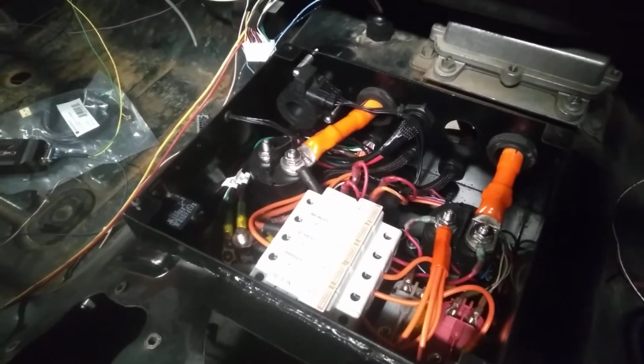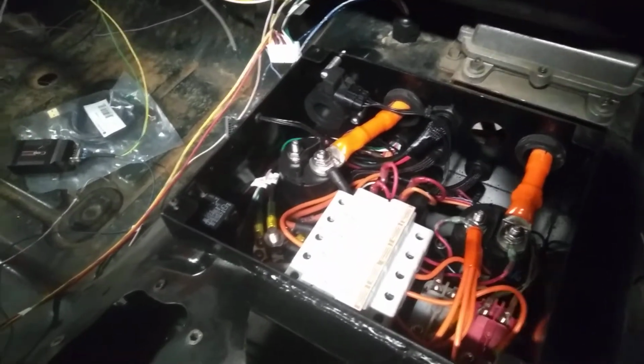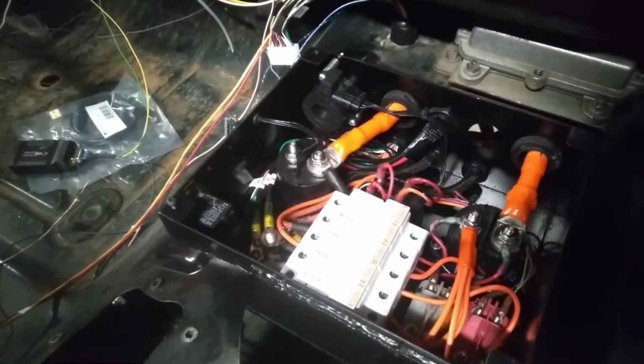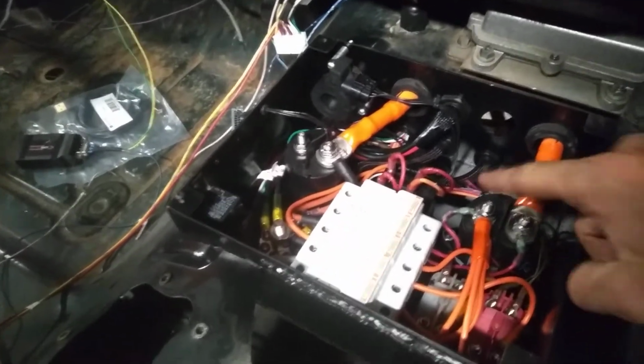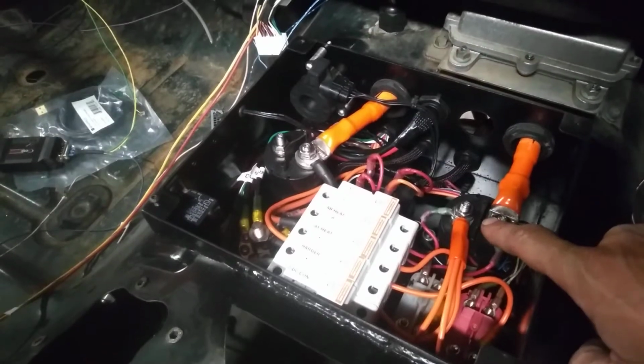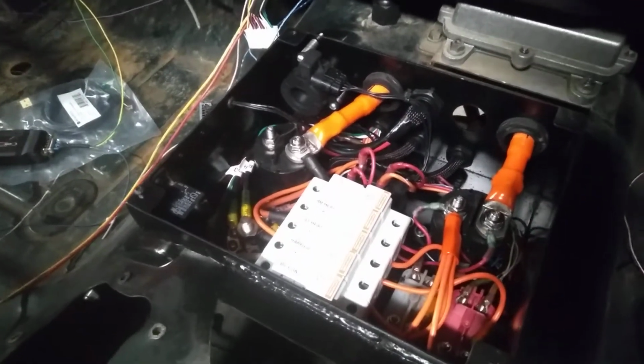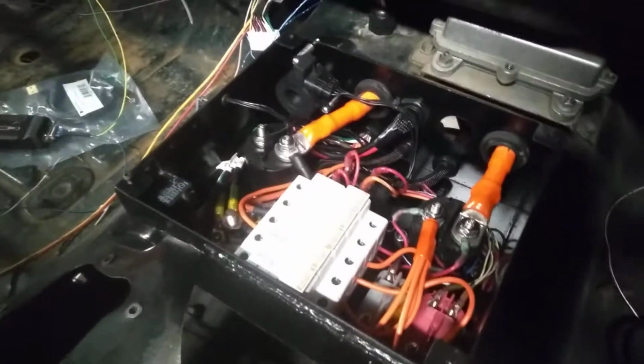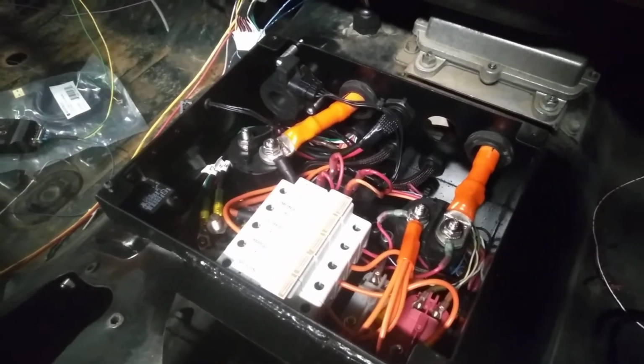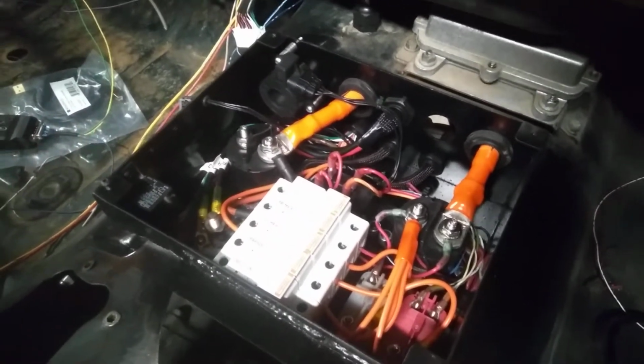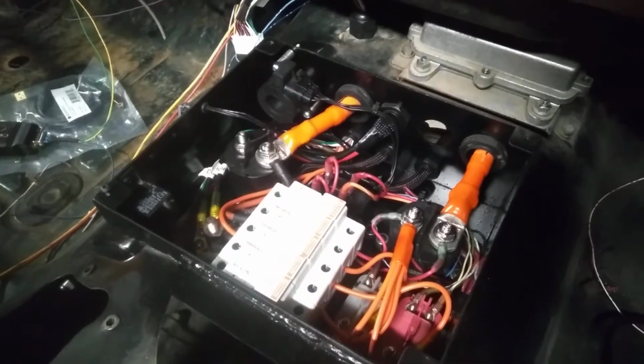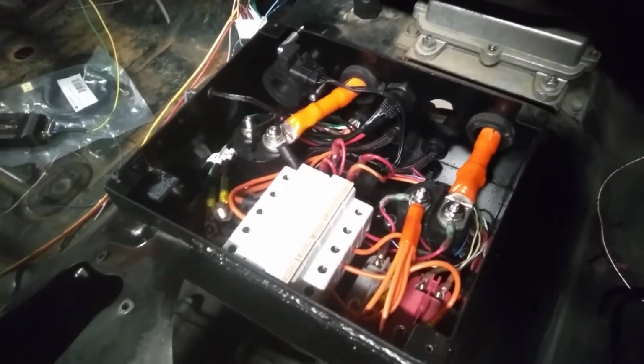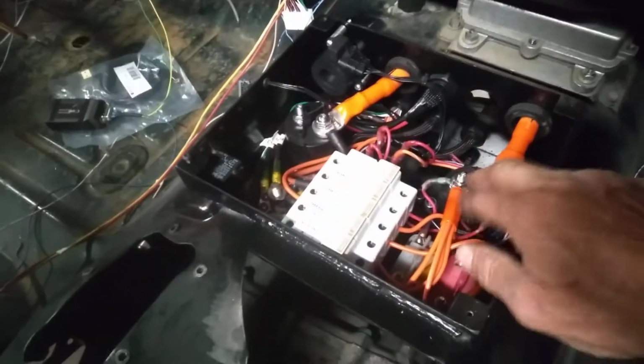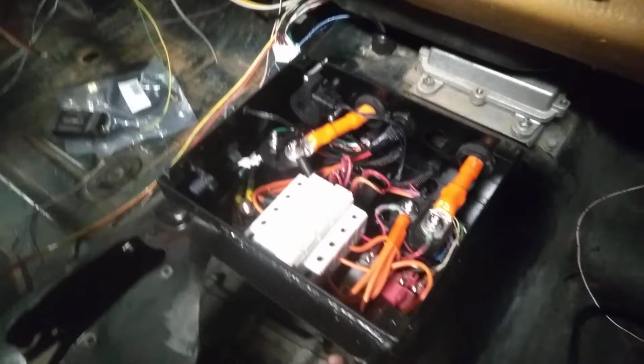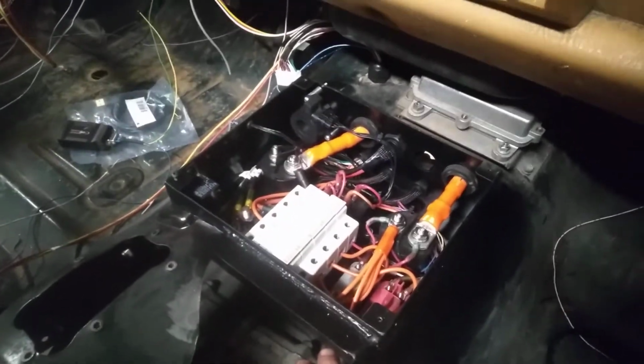If it wasn't for that pre-charge putting current slowly into those capacitors, this contactor closing would basically be a short. Whenever you charge a capacitor, it's basically a short as far as the battery is concerned until the capacitor is full, and then it's nothing - just a full capacitor. But it makes a big fat spark and welds contactors. Not good. So that's that.